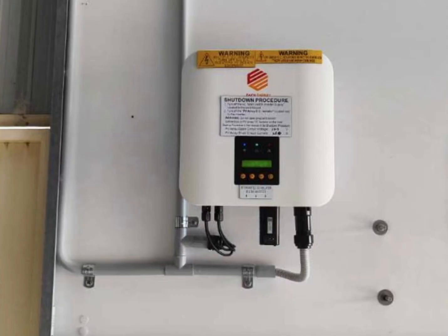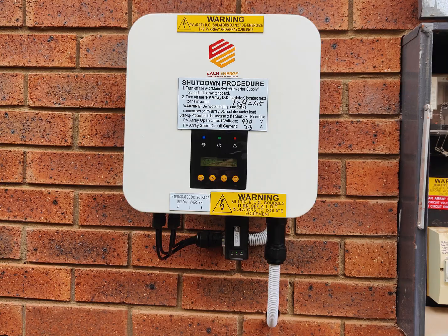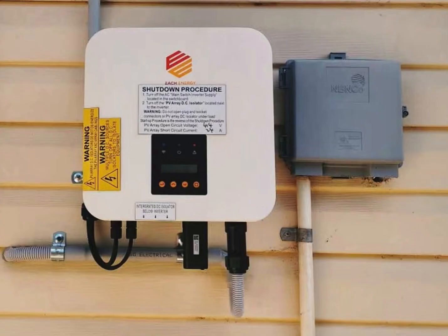Some brands do this part perfectly, such as SolarEdge and Each Energy. Each Energy in particular has made sufficient consideration in the design of the AC output side. For all models less than or equal to 10 kilowatts, AC wires can be directly plugged into the AC conduit with 20 millimeters diameter. Each Energy also gives different reference values for different models with appropriate conduit size and AC switch size.